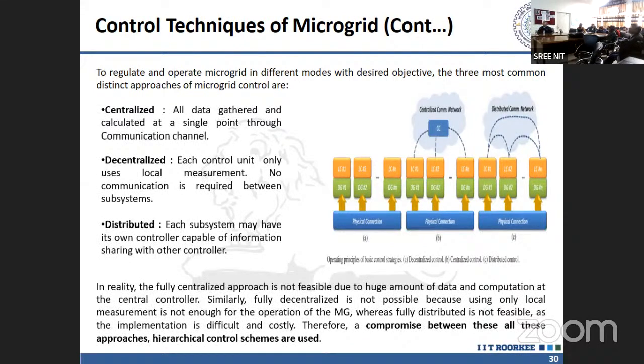The control techniques used in microgrids are centralized, decentralized and distributed. In centralized, all data are gathered and calculated at a single point. In decentralized, each control unit only uses local measurements, and no communication is required. And in distributed, each subsystem may have its own controller capable of information sharing with other controllers. So this is the distributed, this is centralized, and this is decentralized.